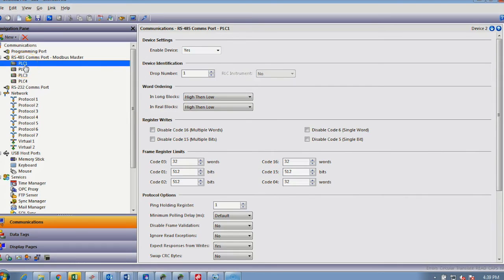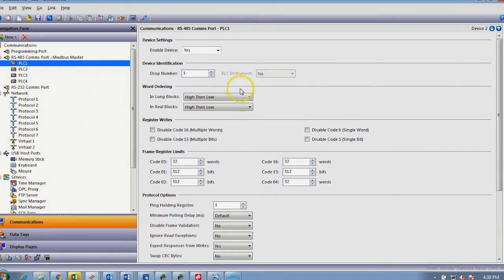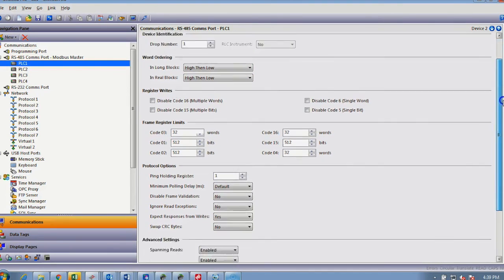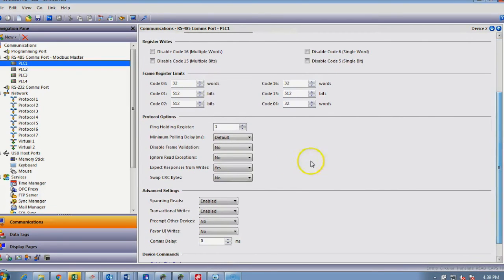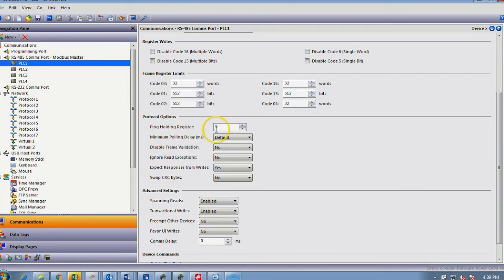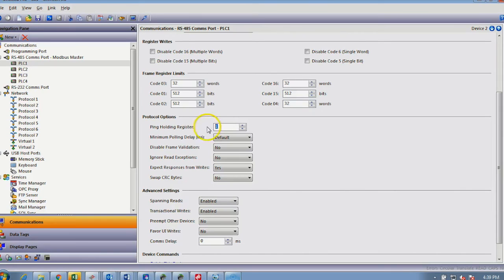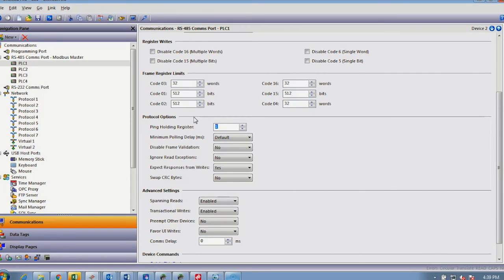Once you have a device itself in place, you have the settings of the device, such as its node number, word ordering, your limits on your framing. And for more advanced settings, we have the protocol options themselves. One in particular, especially for Modbus, is the ping holding register. This needs to be a valid register in the 40,000 range. In this instance, 40,001 for the backbeat, if you like, to actually acknowledge that devices on a network are online—very handy if you need to have subsequent functions if a device is to disappear from a network.